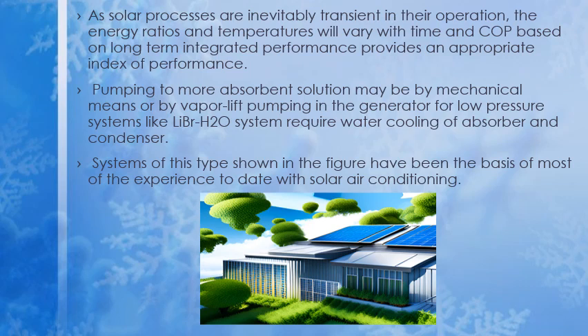We can see the image in the next slide, and before that, the coolers which are used in most experiments are the lithium bromide and water machines, with water cooled absorber and condenser. The pressure in the condenser and the generator is fixed largely by temperature drops across heat transfer surfaces in the generator and the condenser. The pressure in the evaporator and the absorber is fixed by the temperature of the cooling fluid to the absorber and by the temperature drop across the heat transfer surfaces in the evaporator and the absorber. Thus, to keep the generator temperatures within the limits imposed by the characteristics of flat plate collectors, the critical design factors and operational parameters include effectiveness of the heat exchangers and coolant temperature.